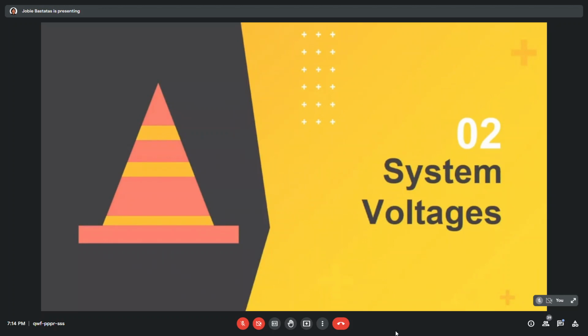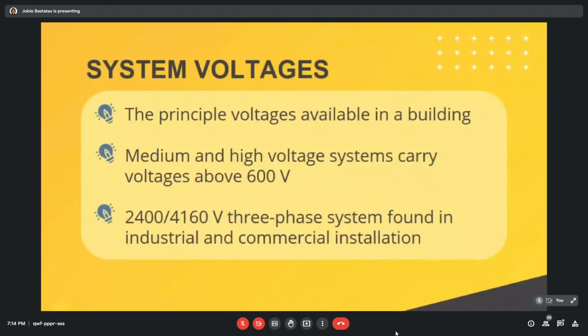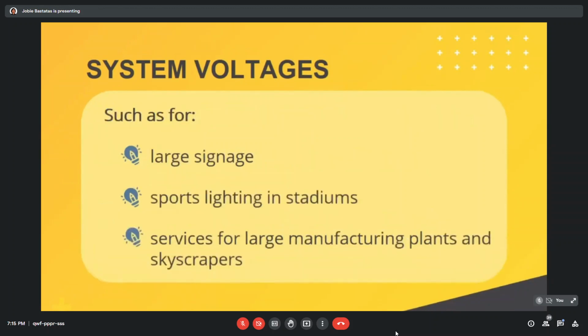Next is system voltages. What is system voltages? System voltage is the principal voltage available in a building. Medium and high voltage systems carry voltages above 600 volts. They may be used in special cases such as the 2400 over 4160 volts three-phase system found in industrial and commercial installations, such as for large signage, sports lighting in stadiums, and services for large manufacturing plants and skyscrapers.